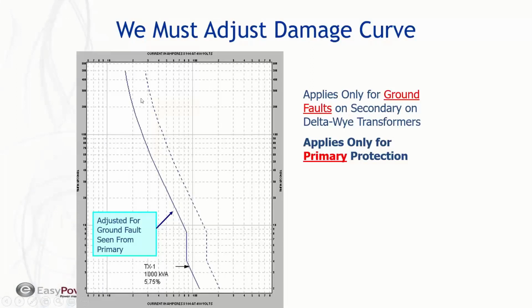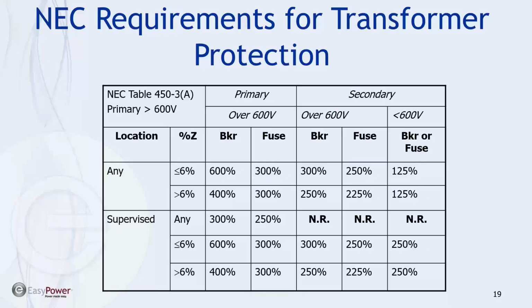And so you'll see in the tools we have a second curve then, and in EasyPower the dotted line is the 100% damage curve, and the solid line is the 58% derated curve. Again, it only applies for ground fault protection on the secondary side and ground fault on the secondary side, and the protection installed on the primary side.